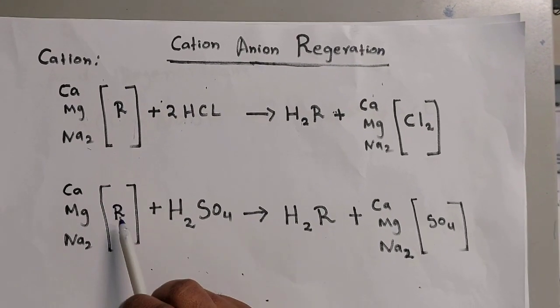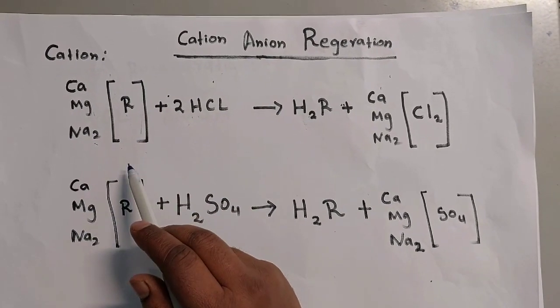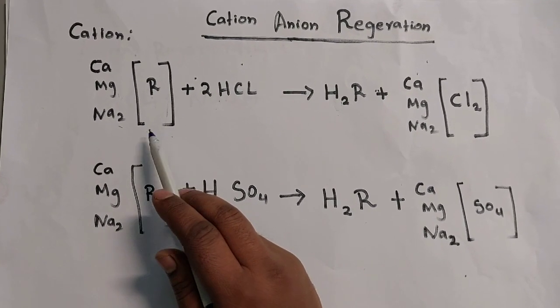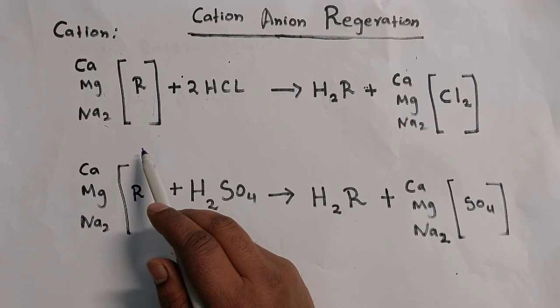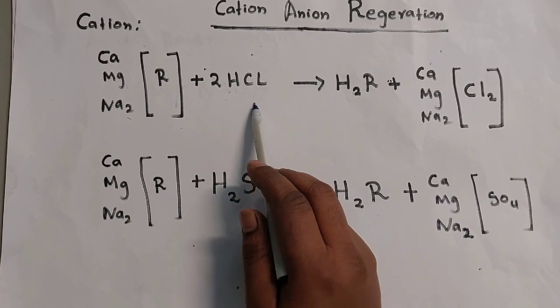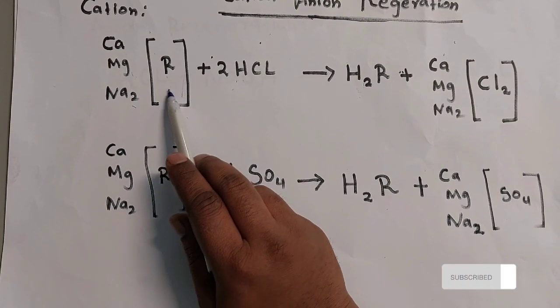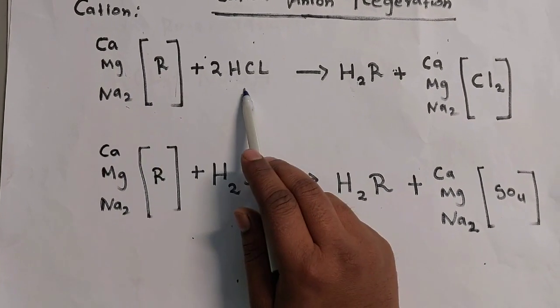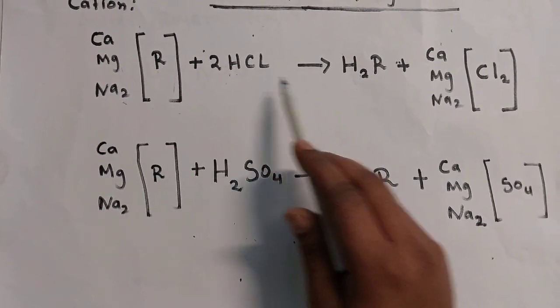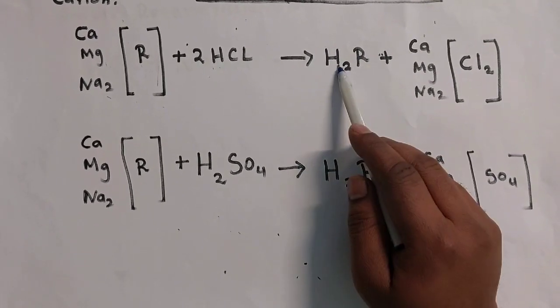The cation resin absorbs all the positive ions, so the resin is going to be exhausted — means saturated. All these saturated resins we need to clean and make pure again. We are making regeneration by using hydrochloric acid or H2SO4. For example, using hydrochloric acid: calcium, magnesium, sodium — everything present in the resin — all we remove. They react with the hydrochloric acid. Calcium chloride, magnesium chloride, sodium chloride go to separate. Finally we find the pure resin again. This is the regeneration.